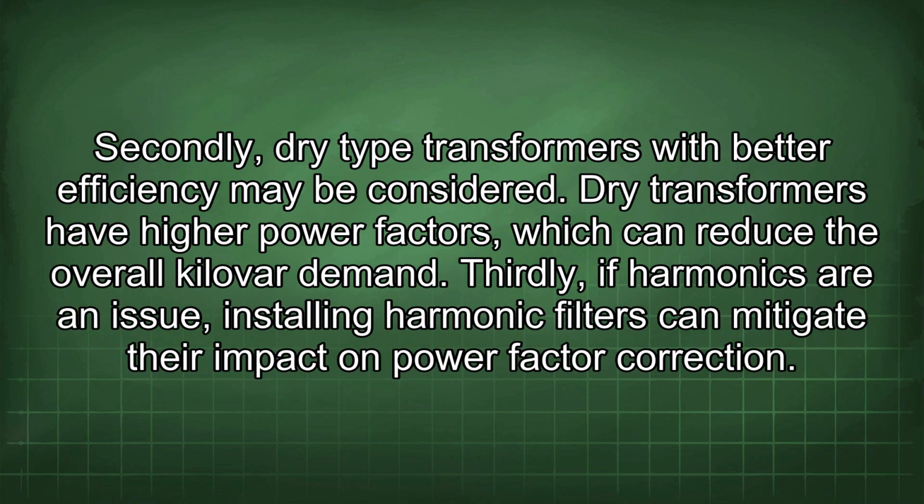Secondly, dry-type transformers with better efficiency may be considered. Dry transformers have higher power factors, which can reduce the overall kilovar demand. Thirdly, if harmonics are an issue, installing harmonic filters can mitigate their impact on power factor correction.